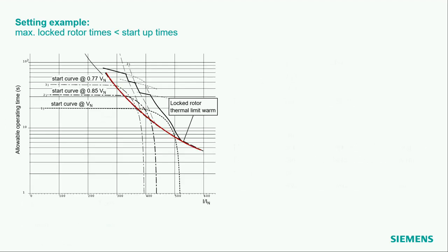Although it's not necessary, here I have another example of a motor. Here the locked rotor thermal limit, this red curve, so I enhance this by drawing this red curve here, is smaller than the start curve. You see here the starting time is like this value here, 2 seconds. No, these are 10 seconds, 20 seconds. You see this is a rather big motor. And the smaller the voltage is, the bigger is the starting time, and of course the smaller is the starting current.